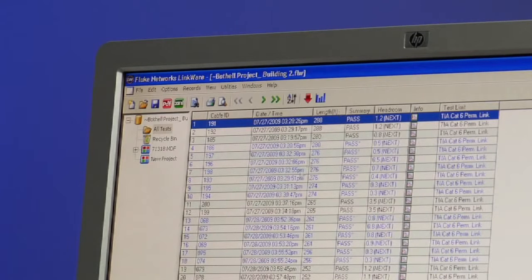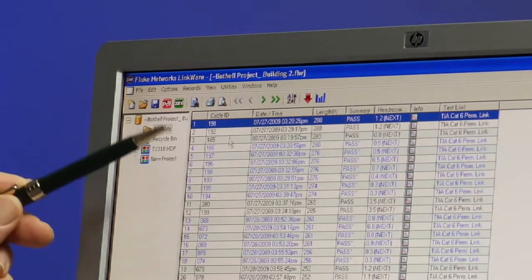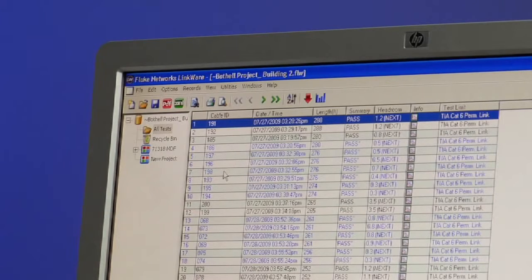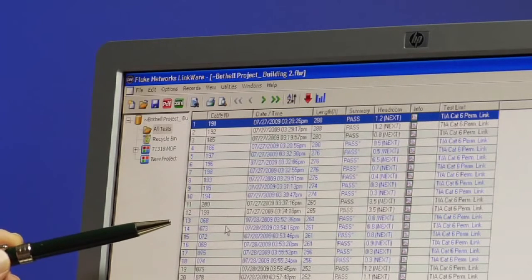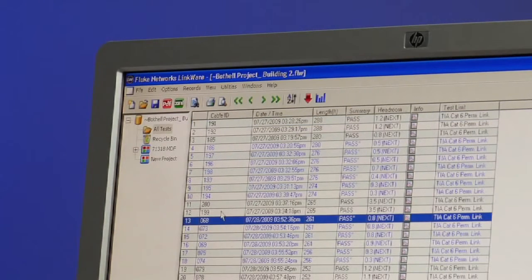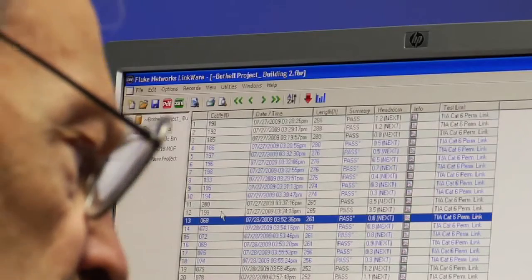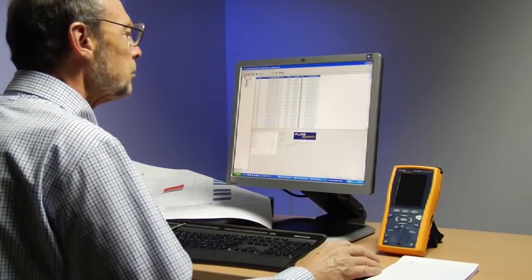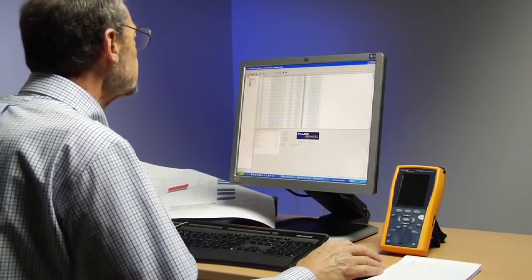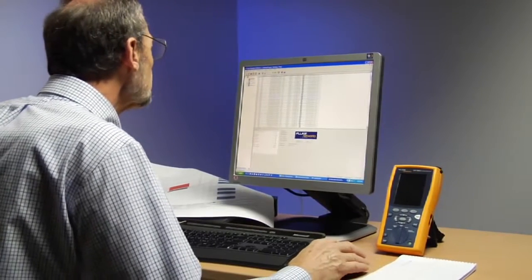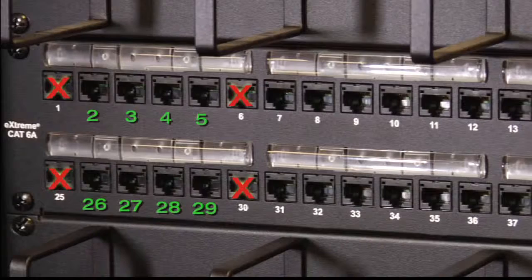The first step is to sort all the in-channel test data records by length. We want to choose the longest link because it's the most susceptible to alien crosstalk interference. In addition to the length of the links, we should also pick links from the different bundles to get a good sample. If we know how our links are routed and the bundle quantity is kept to a minimum, it'll make alien crosstalk testing easier.